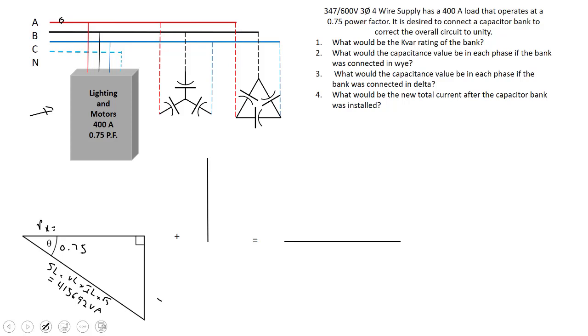It's going to come to about 311,769 watts. From there I could use Pythagorean theorem or I could convert the power factor to angle and then use sine theta multiplied by our apparent power. Either way, you can get lagging VARs of that panel is going to be around 274,954 VAR.